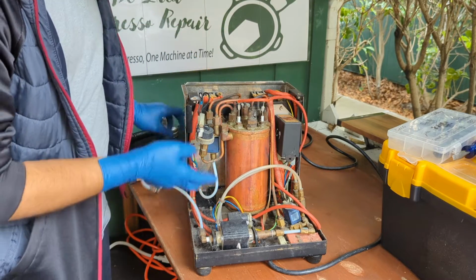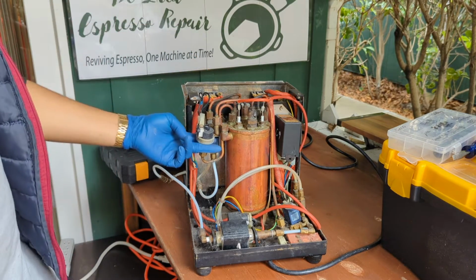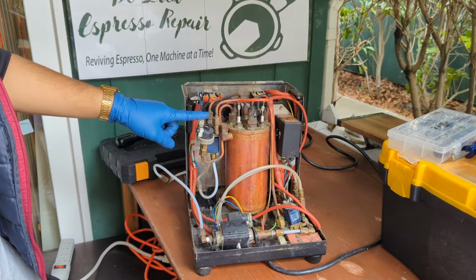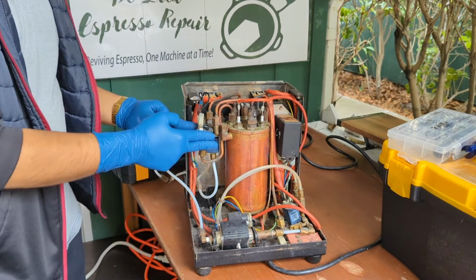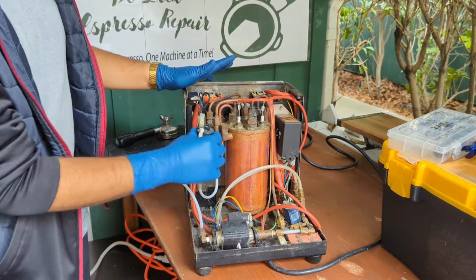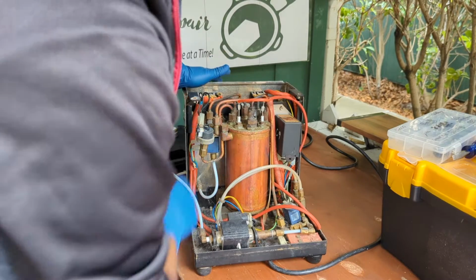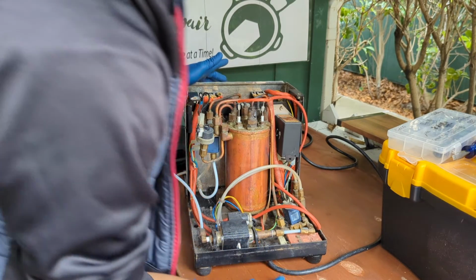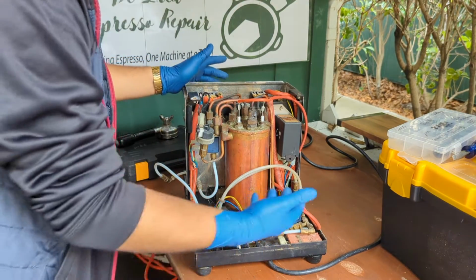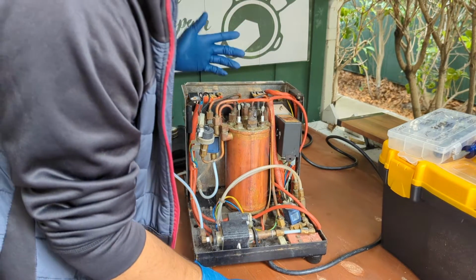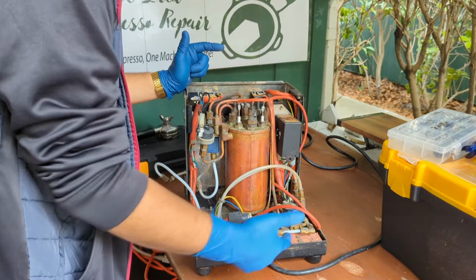So the pressure stat - this probably is what was causing the machine to overheat. We're gonna have to replace that as well, as I don't want to be dealing with the old pressure stat from 1997. As for the flow meter, if this thing even has it - which I highly doubt, because there's nothing for this machine to know about water going through it - so I don't see a flow meter.